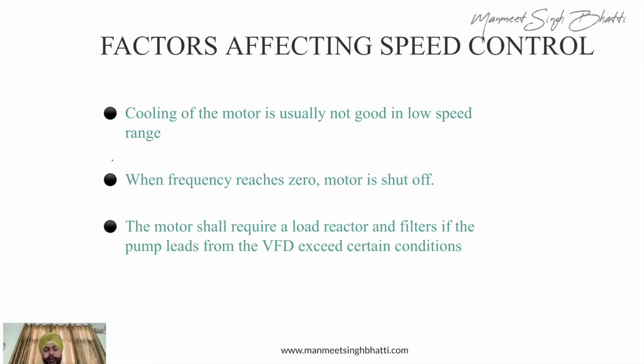Now, when the frequency reaches 0, the motor is shut off. So this is very important because the frequency controller is giving you an output. Although you can lock in the frequency, like you can have an RPM not lower than 30%, below that the motor will keep on running. But there is a challenge. Sometimes you have a safety application and the control requirement actually takes the frequency to 0. So there is a possibility of the motor getting stalled, so the motor getting shut off.